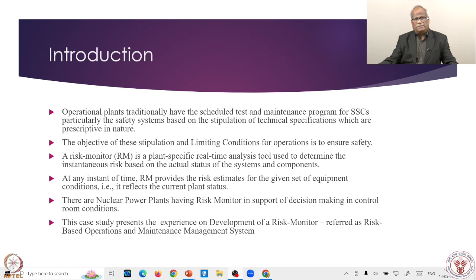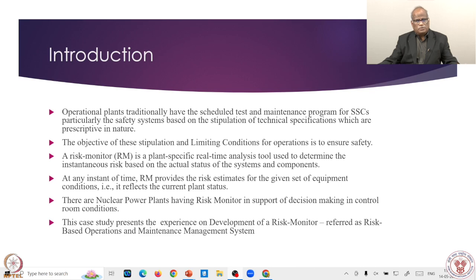At any point in time, the risk monitor provides a risk estimate for a given set of equipment conditions — it reflects the current status of the plant. For example, if one diesel generator is under maintenance and the criterion is two-out-of-three diesel failure equals system failure, then that has to be apportioned: one of three is unavailable. A simulation is carried out, and nowadays simulators are available so you can do parametric studies to see the impact of various plant and system configurations.